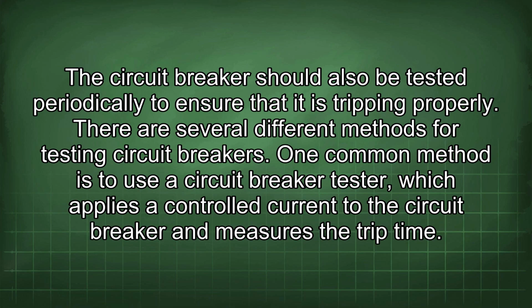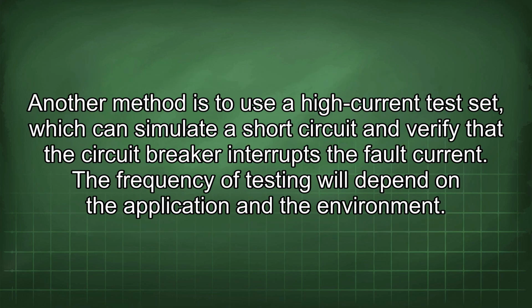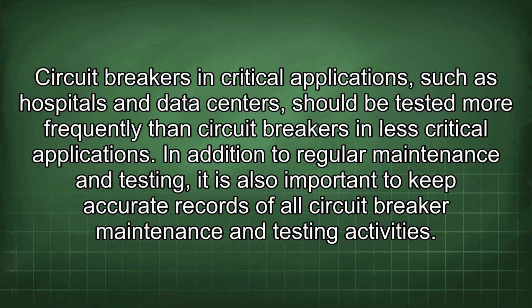There are several different methods for testing circuit breakers. One common method is to use a circuit breaker tester, which applies a controlled current to the circuit breaker and measures the trip time. Another method is to use a high current test set, which can simulate a short circuit and verify that the circuit breaker interrupts the fault current. The frequency of testing will depend on the application and the environment.